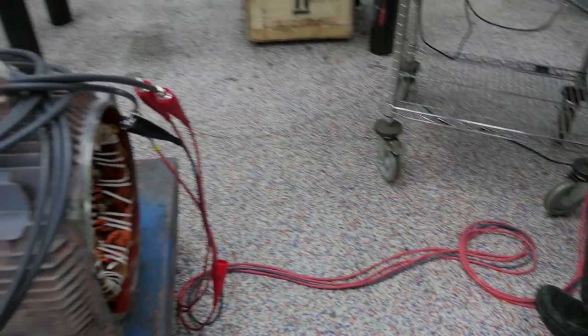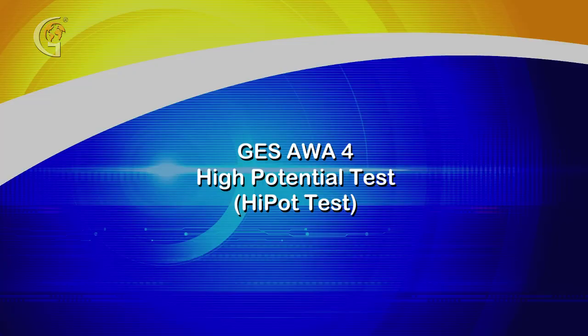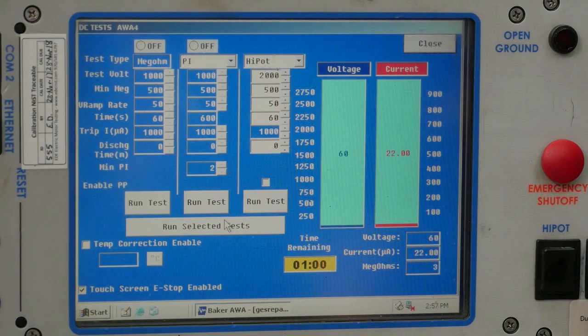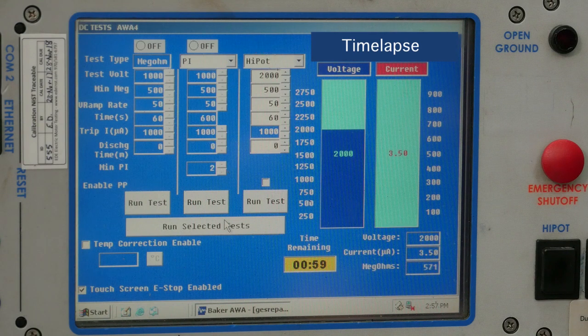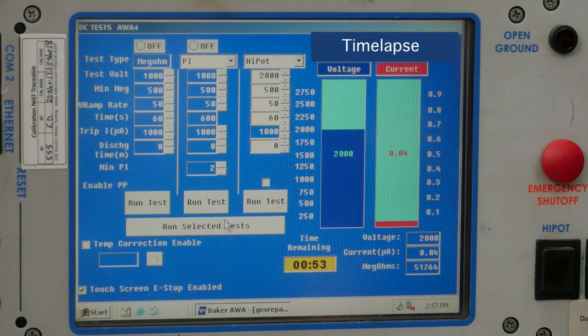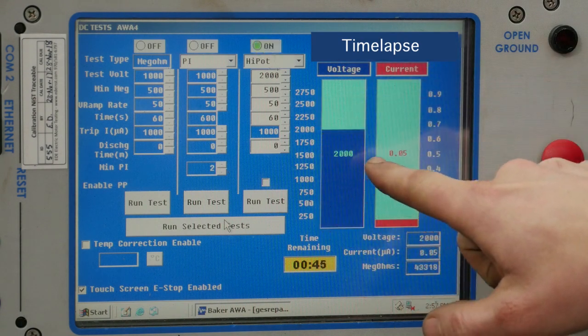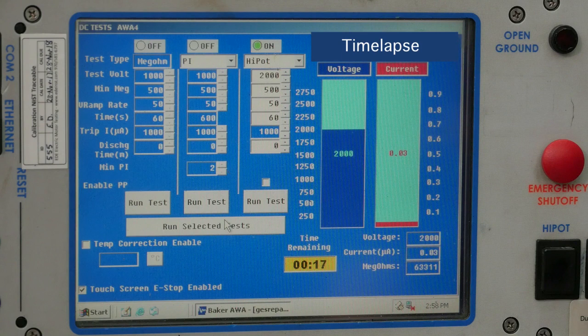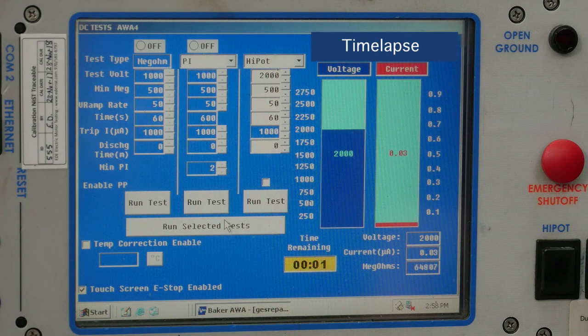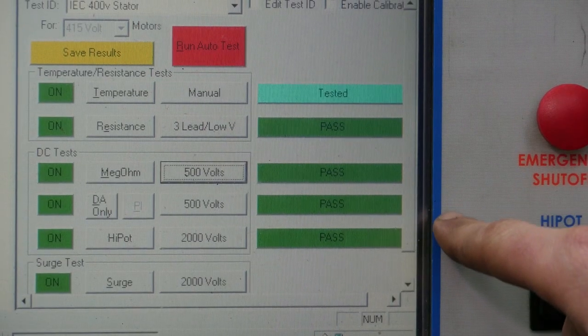Our testing now moves to the next test. The last test in this series is the high pot test. A high pot, or high potential test, injects voltages higher than a mega-ohm test, which simulates what the motor would experience during startup. Here, we see that 2,000 volts are being applied, and here we can monitor the current. If high leakage current is detected, this could mean a failure within the motor ground wall insulation. This test has passed.